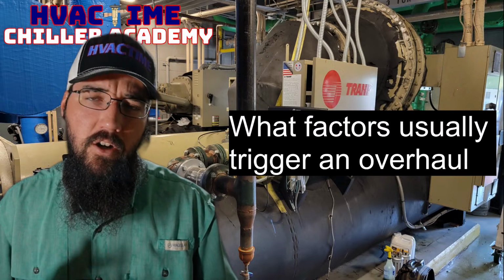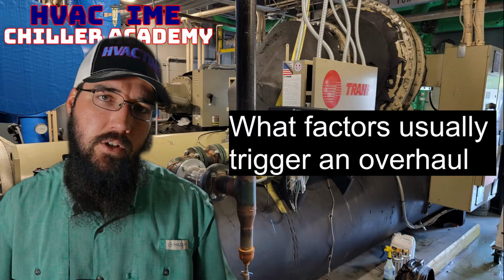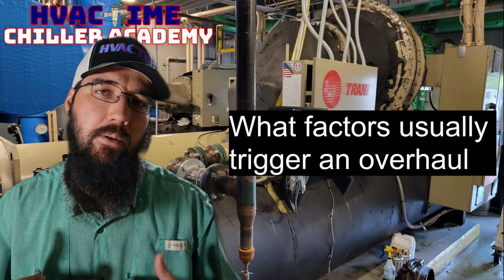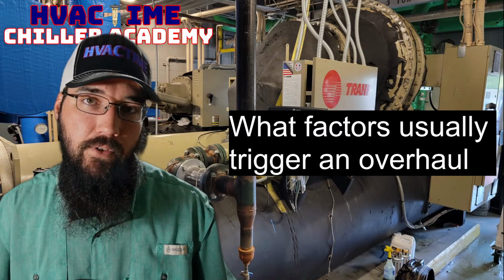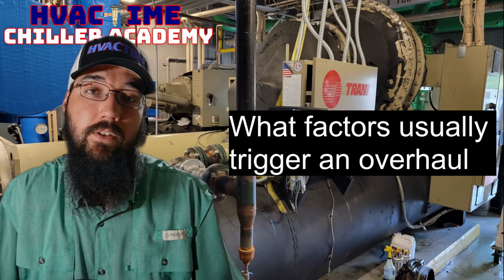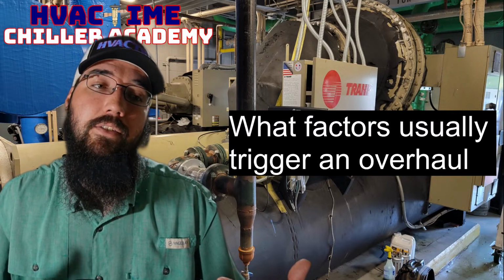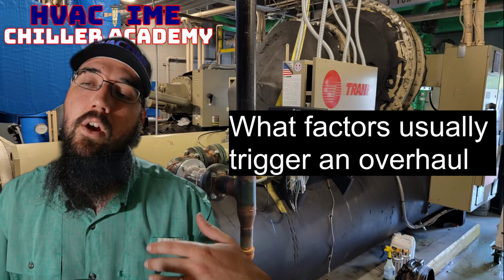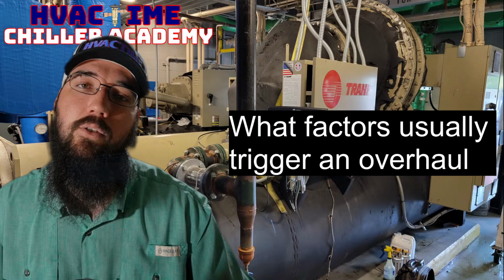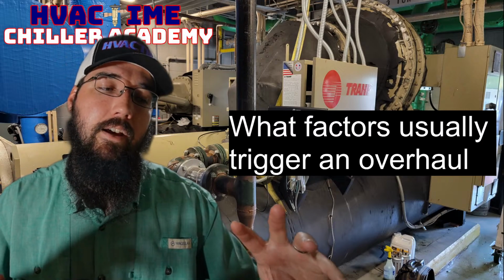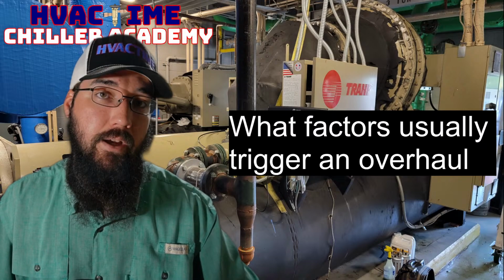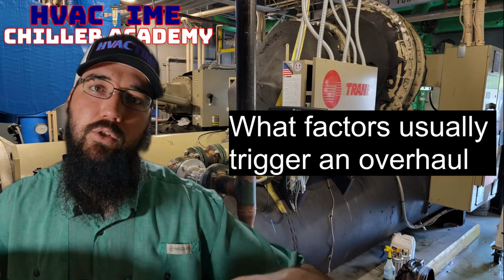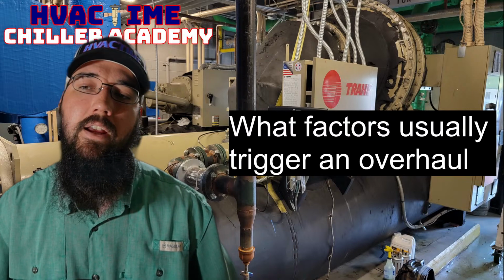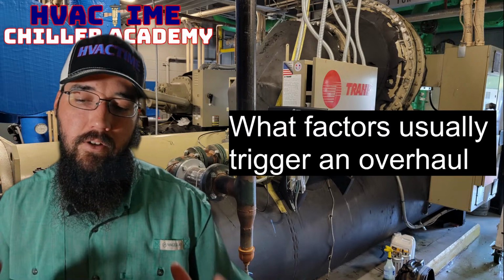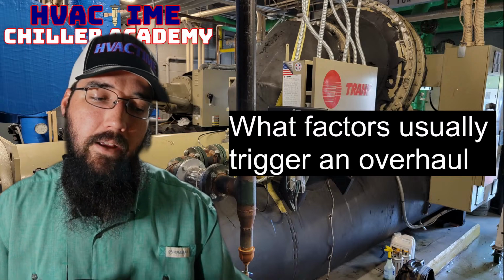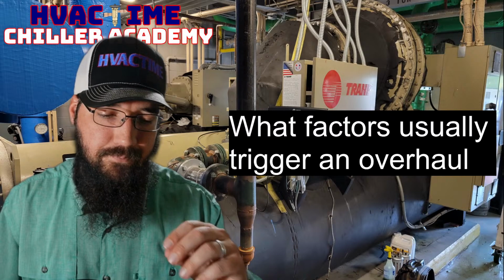So there are other things though. If we're having trouble getting lift and moving the refrigerant, and the machine is even having trouble to function, we could be having an impeller issue. There could be something like we may have had a touchdown and we messed up some of our vanes, or we could have slugged back or had droplets come back and start shredding the internal of the impeller, right? So we ran our liquid levels too high, or something happened on the load side that allowed us to mess up the impeller by allowing liquid refrigerant to come back in.